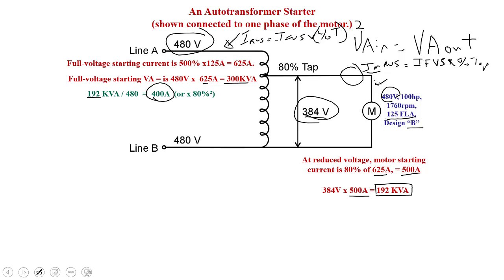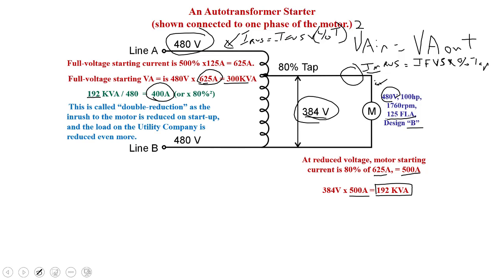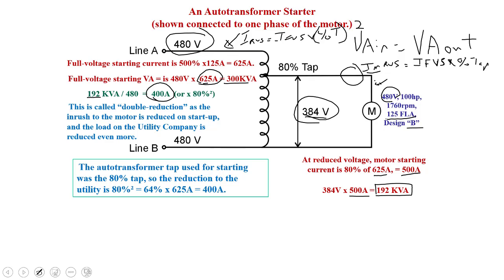So if I took 625 amps and multiplied it by 0.8 squared, I would get 400 amps. Once again, this is referred to as a double reduction. The auto transformer tap used for starting was 80%, so the reduction to the utility, the line side of the auto transformer, is 80% squared. Essentially 0.8 squared means 64%. So 64% of 625 is 400 amps.